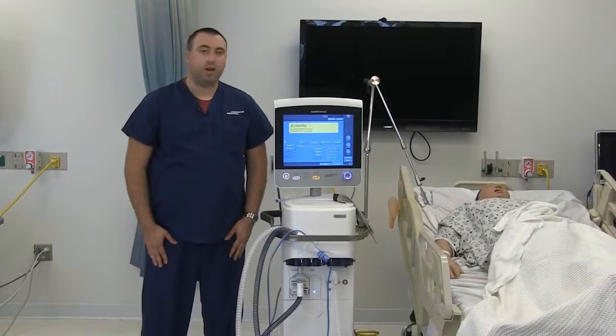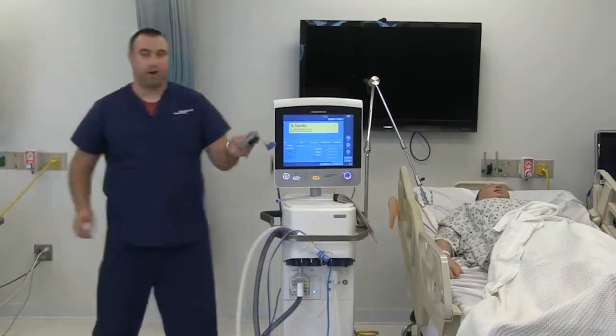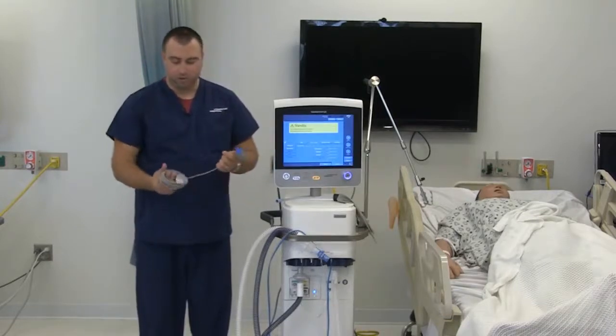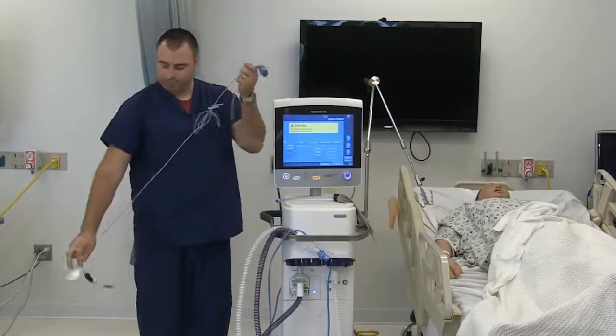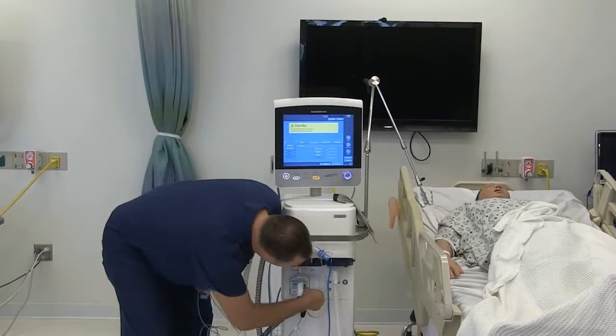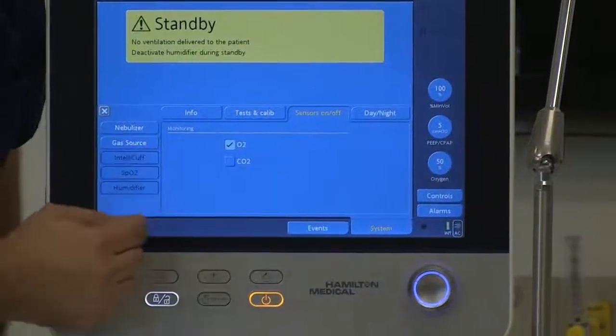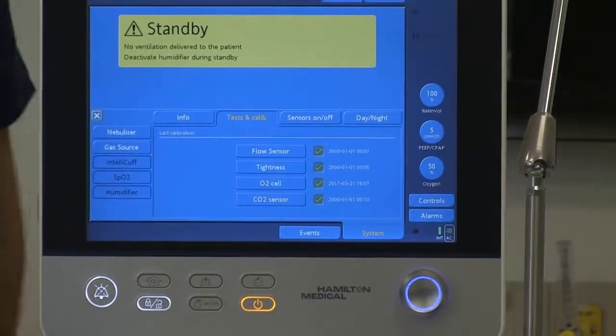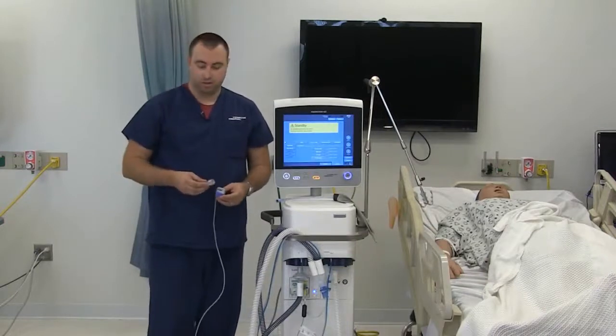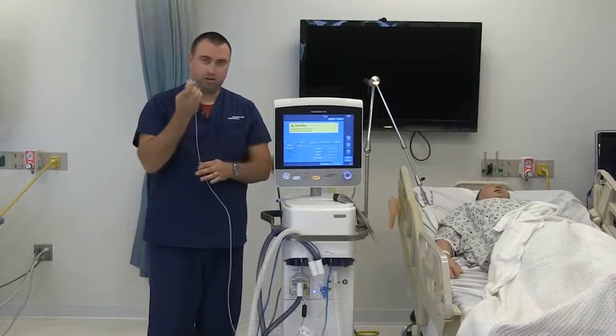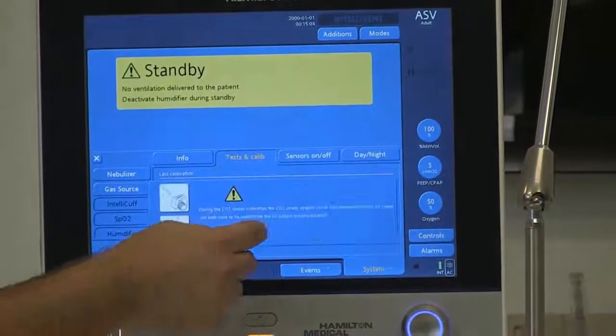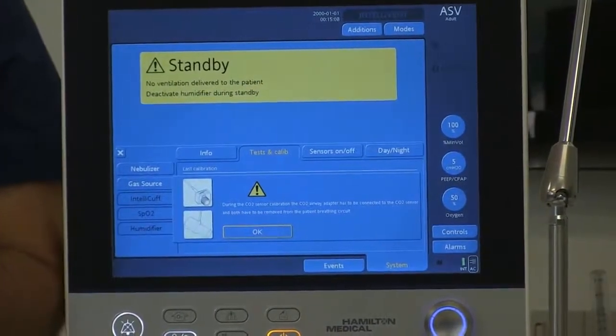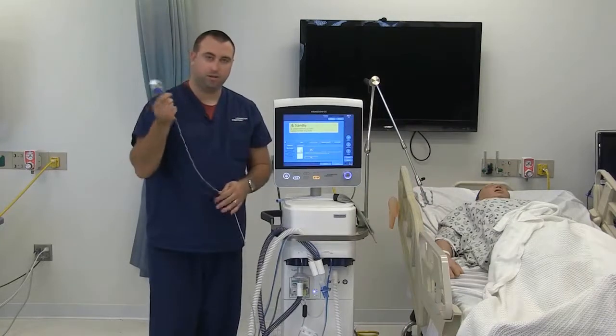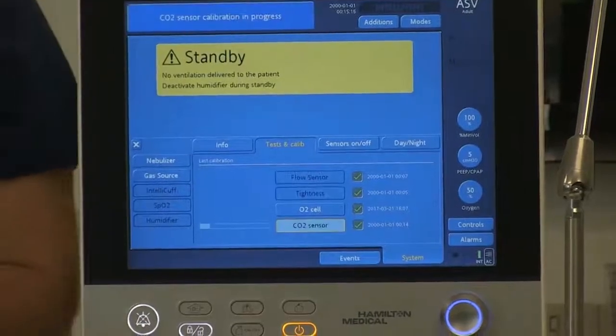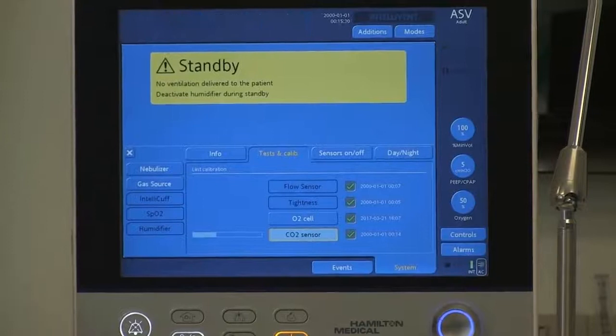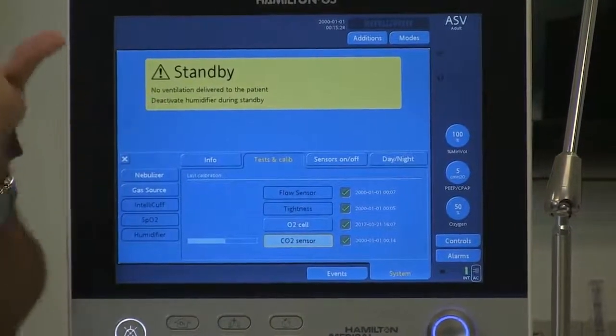To activate your CO2 sensor and calibrate it, you will need a CO2 sensor wire and your airway adapter. So what you do is you just unravel it, plug it in down here into your CO2 port, go up to sensors on off, activate your CO2 sensor, back to test and calibration. To calibrate your CO2 sensor, you take your airway adapter, place it into the port, hit CO2 sensor calibration. We'll give you a picture telling you to place your adapter in and have it out of the circuit into room air. You hit OK, and it takes about 20 seconds to calibrate. And when it does, it will tell you the CO2 sensor will be completely calibrated.